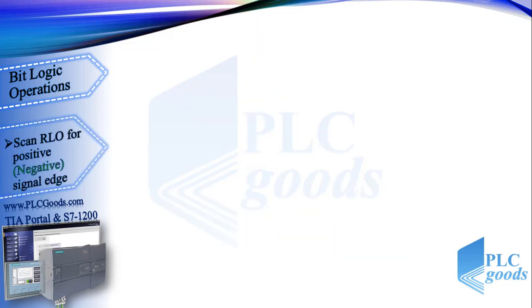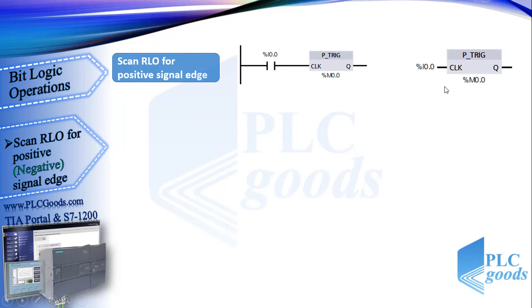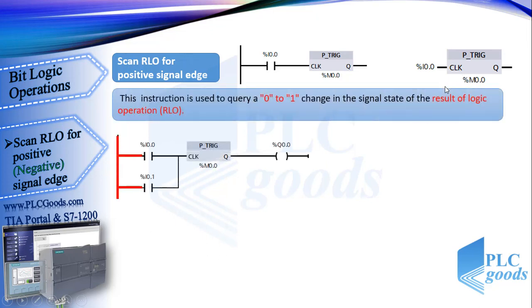Now I want to explain an instruction which scans RLO for positive signal edge. This is its ladder symbol. Unlike the previous instruction, this only needs one memory address to work correctly, and this is its FBD symbol. This instruction is used to query a 0 to 1 change in the signal state of the result of logic operation, RLO.